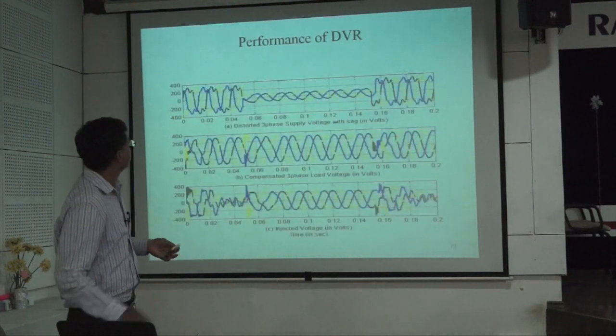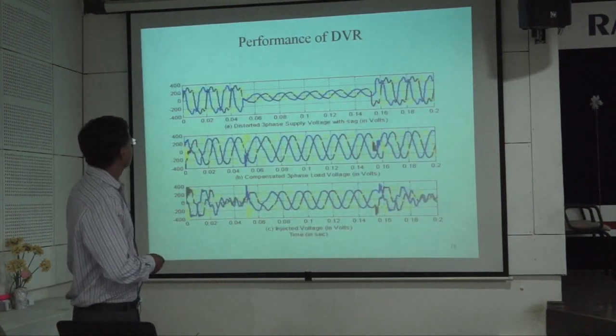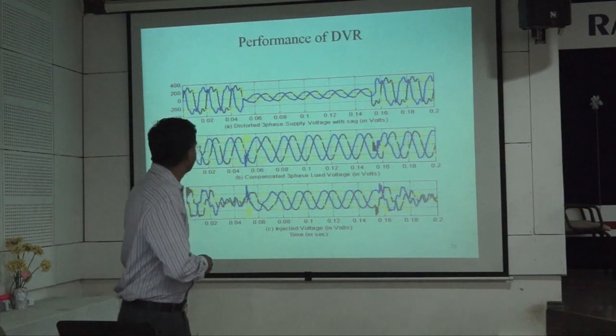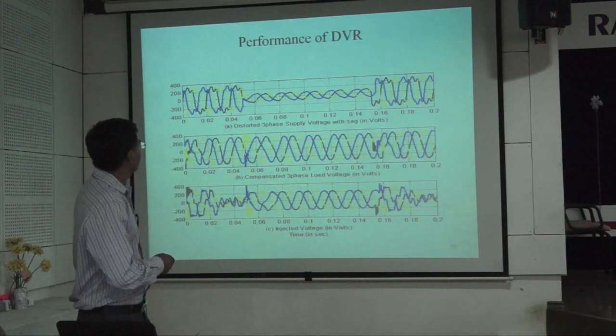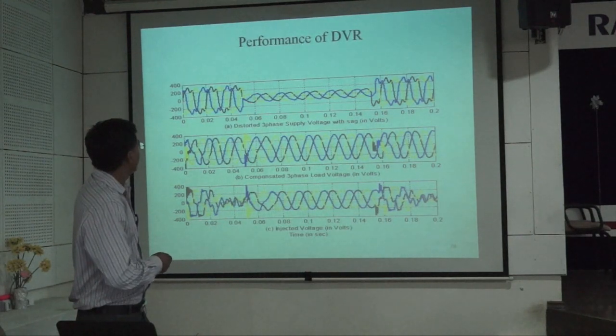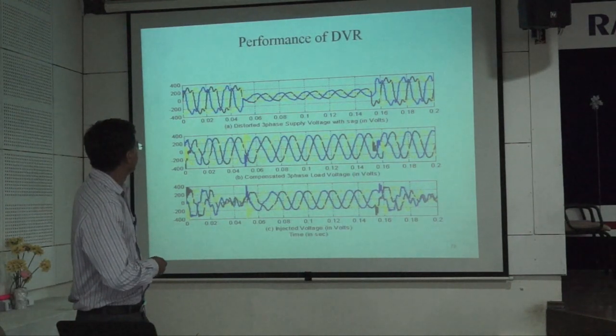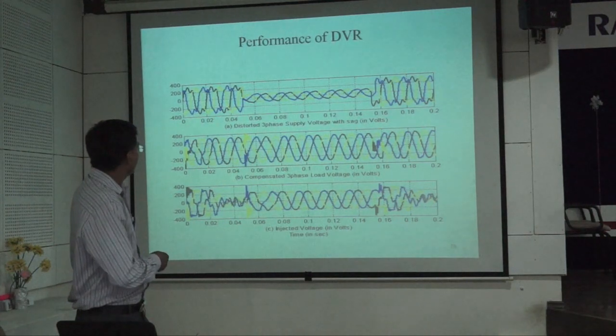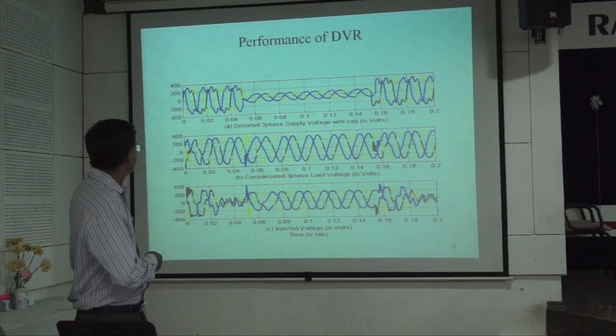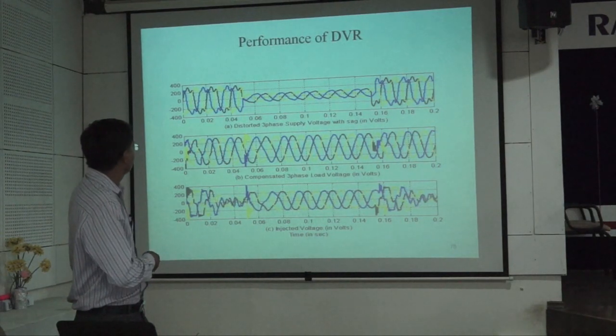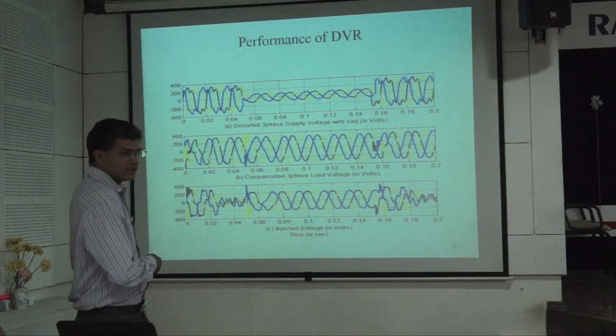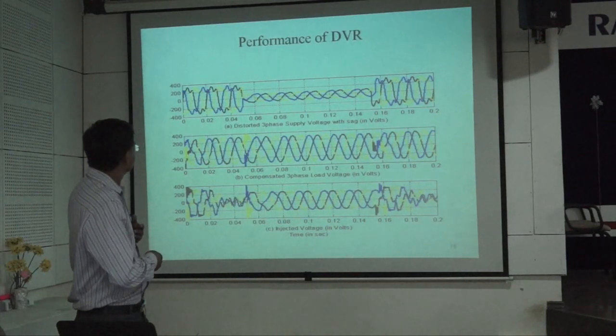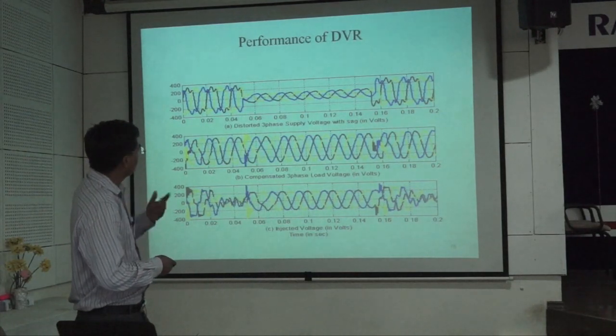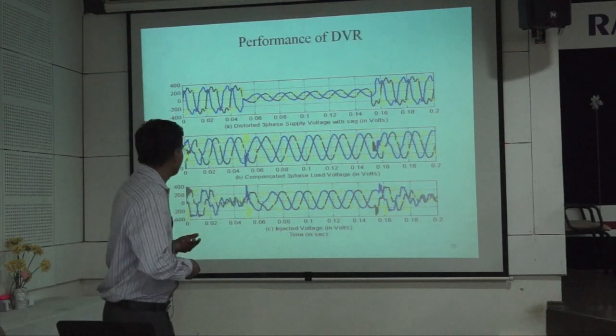It is the injected voltage. See the performance during the sag. This is the 3-phase sag. This is the distorted 3-phase supply. Around 60% sag is created for near about 7 to 8 cycles. This is the compensated load voltage, and see the DVR action. DVR is starting from the 0 instant. DVR is in action, so the transients are reduced and the load is maintained at a proper value.